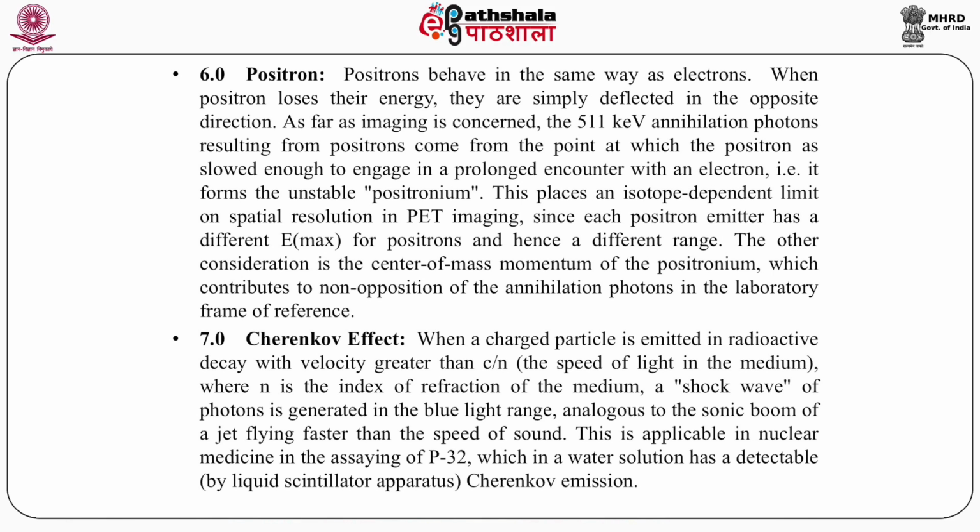This places an isotope-dependent limit on spatial resolution in PET imaging, since each positron emitter has a different E max for the positron and hence a different range. The other consideration is the center of mass momentum of positronium, which contributes to non-collinearity of the annihilation photons in the laboratory frame of reference.